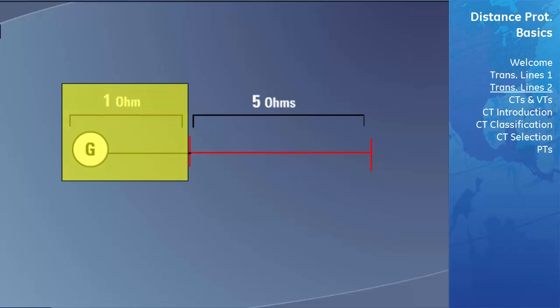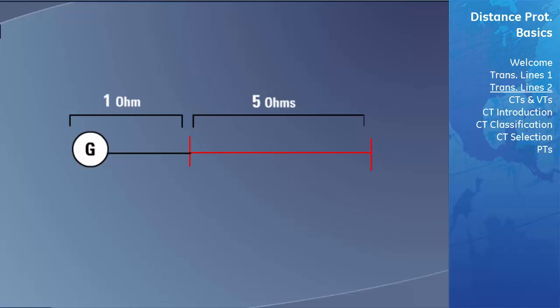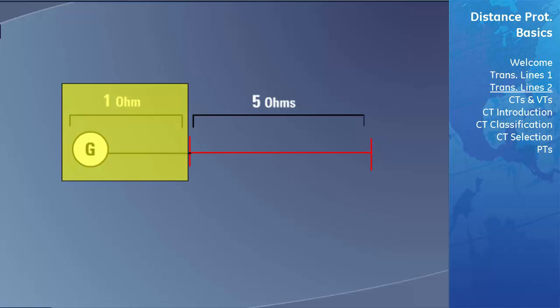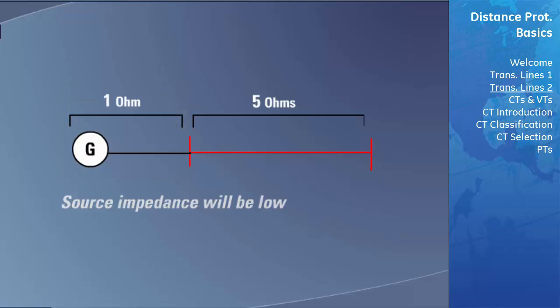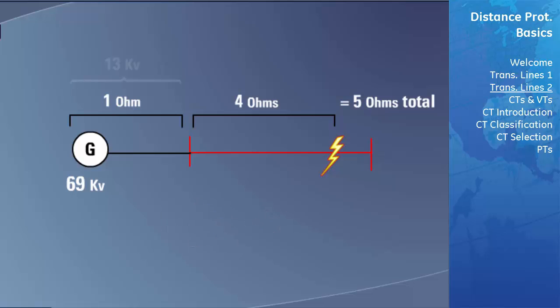The system impedance ratio takes the source impedance — which is the source impedance of the system behind the transmission line — and divides that by the line impedance that you are protecting. If the system behind the transmission line has a strong source, the source impedance will be low. In this configuration, if a fault occurs on the transmission line, the fault current will be very high and the voltage at the location of the PTs will tend to remain stable.